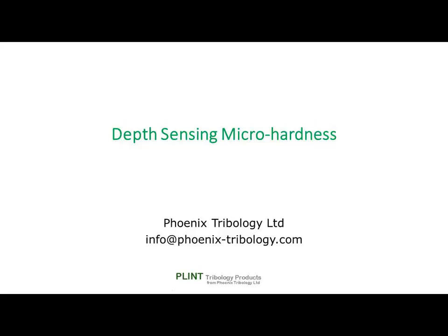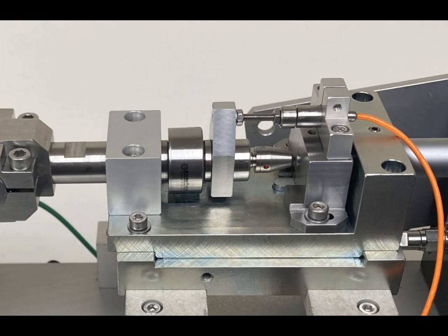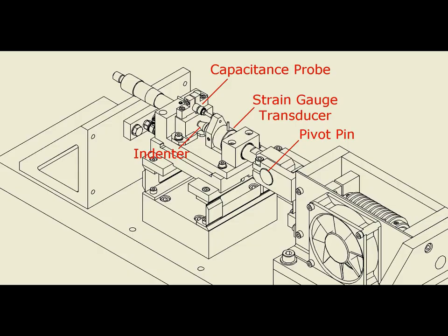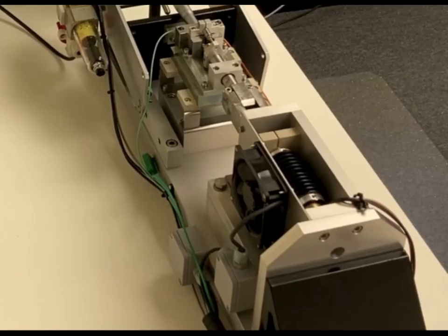Depth sensing microhardness tests are run with a standard Vickers diamond indenter with 136 degree face angle. Depth sensing microhardness requires much higher sensitivity for force measurement than the fretting tests. The moving specimen carrier now mounts a diamond indenter and incorporates a strain gauge transducer.